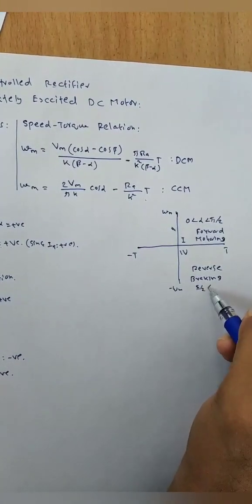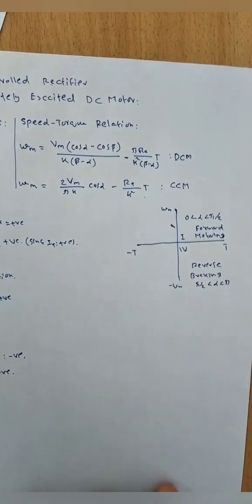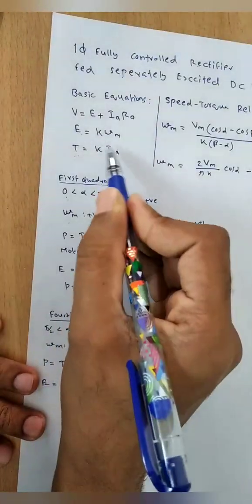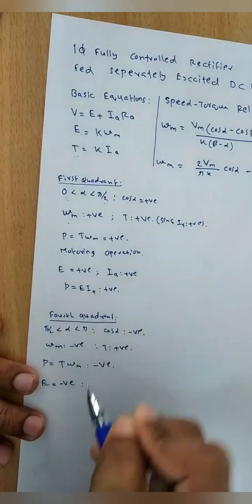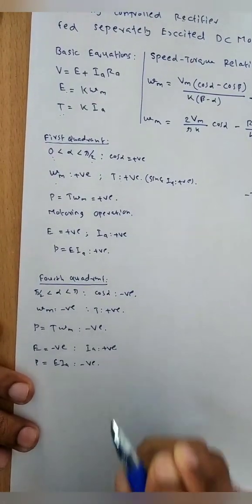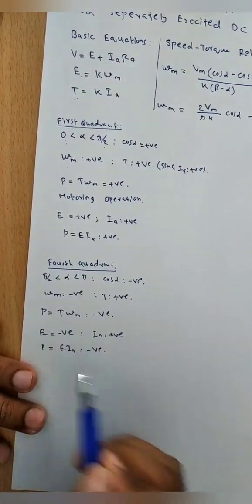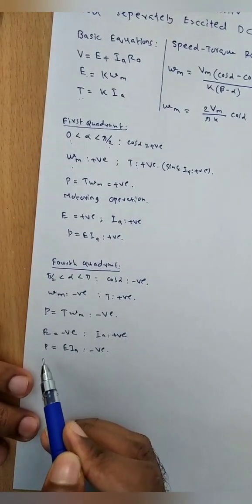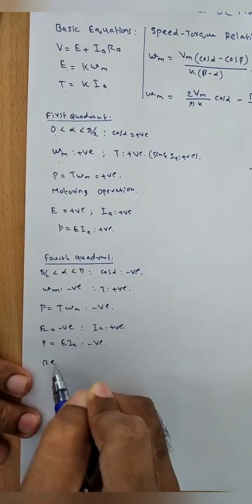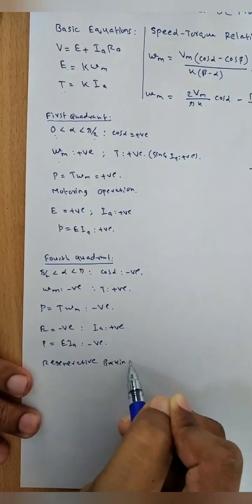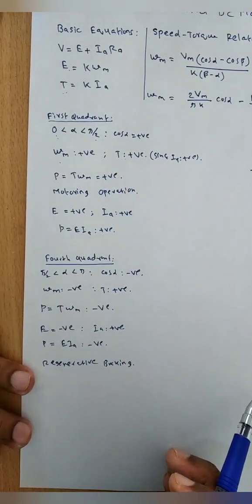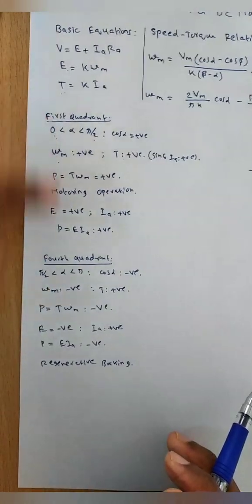This is achieved by controlling alpha between π/2 and π. Since E = K × ω_M and ω_M is negative, E is negative. But i_a is always positive in a controlled rectifier, so P = E × I_a is negative. This is regenerative braking mode. So we can achieve forward motoring and reverse regenerative braking using the controlled rectifier by controlling the firing angle alpha.